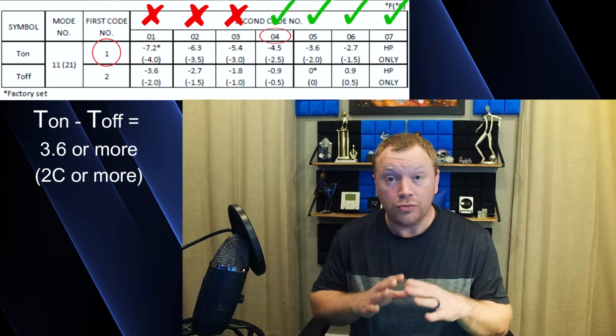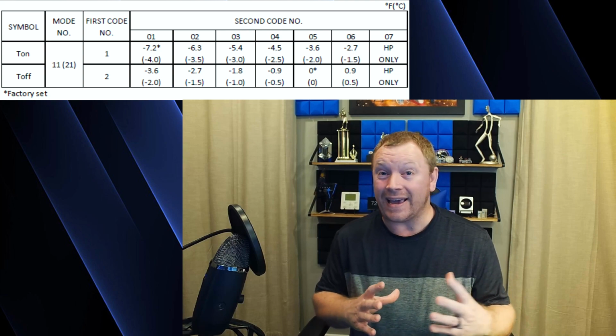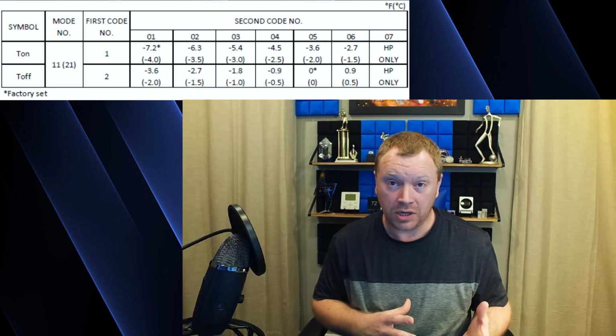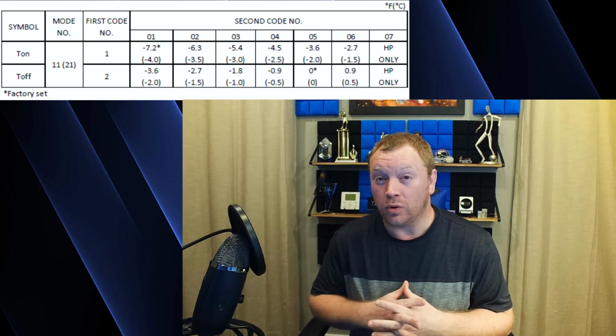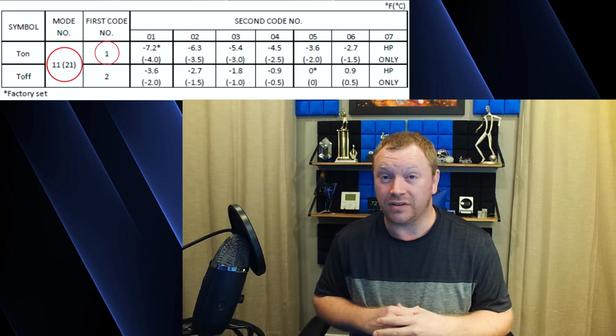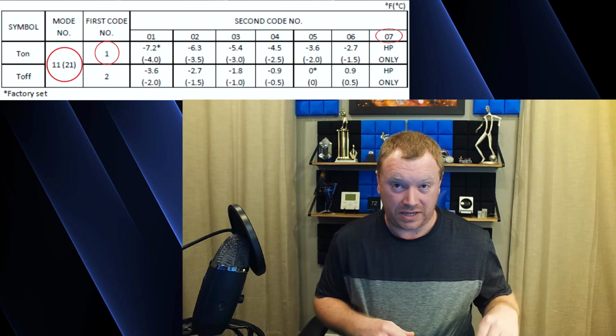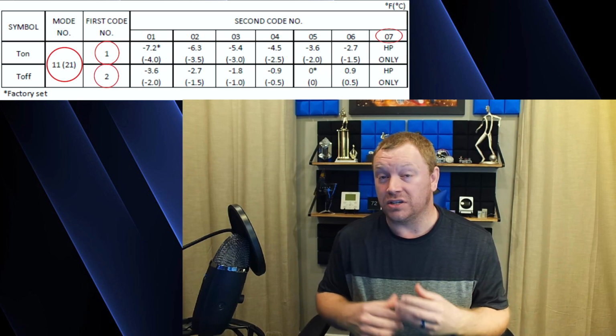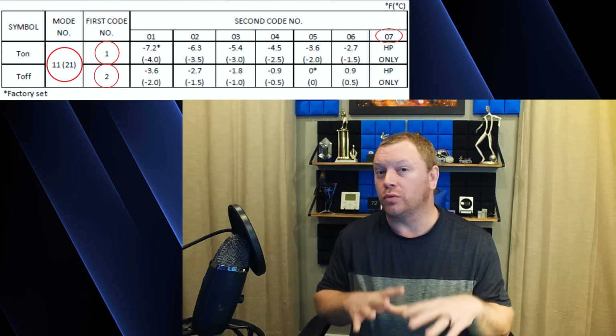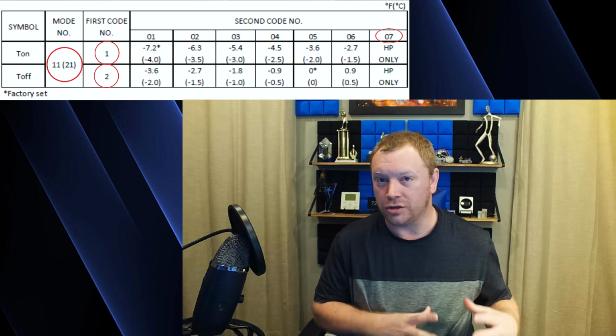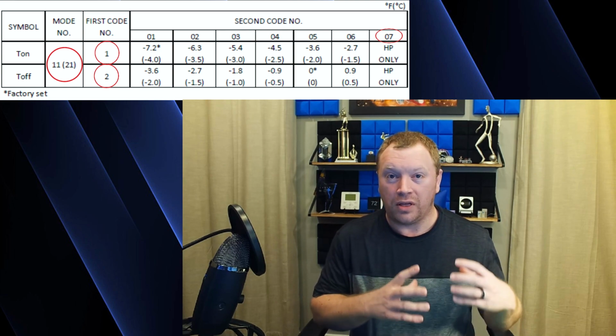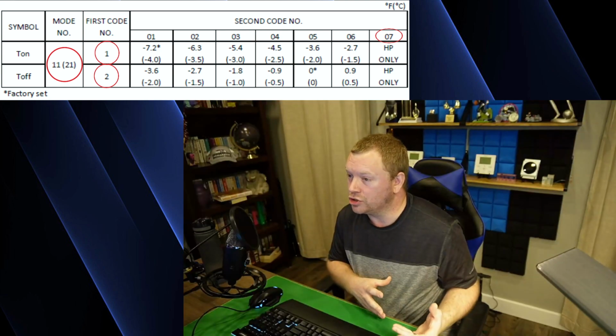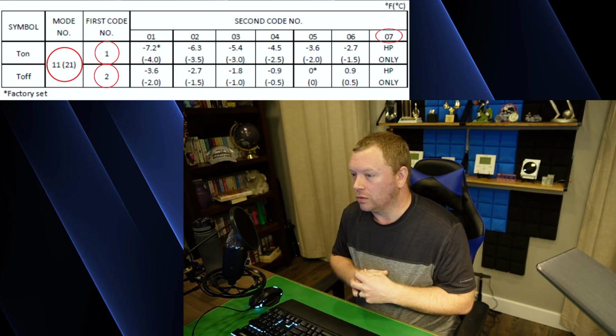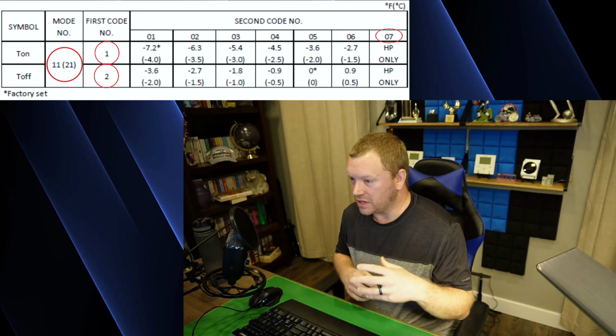Now, if you do not want the gas to come on at any amount below the set point, then you're going to go ahead and program mode 21, setting number 1-07, and mode 21, setting 2-07, and you'll see in this chart it says HP only. That means run the heat pump only. You don't want to use the gas furnace for this type of backup heat. Maybe you're just using the gas furnace for emergency heat purposes if the heat pump fails.